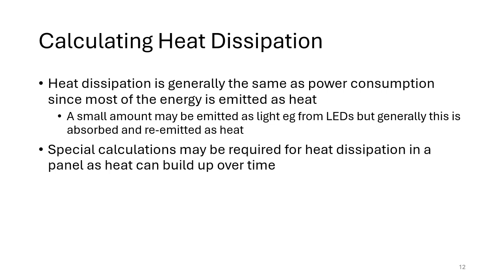A lot of people also want to know what heat dissipation is. Interestingly, heat dissipation is generally the same as the power consumption, since most of the energy that's consumed by the electronic components is emitted as heat. A very small amount might be emitted as light from LEDs. So for example, a typical red LED uses about 10 milliamps, but at a very low voltage, so the actual amount of power coming from LEDs is small. And if we're looking at that energy, we'd also need to think about what's going to happen with it, because it might be light inside the panel, but that light's going to be absorbed by the panel itself and re-emitted as heat. But generally you don't need to worry about light, because the amount of light emitted is so small, it's dwarfed by your other power consumption.